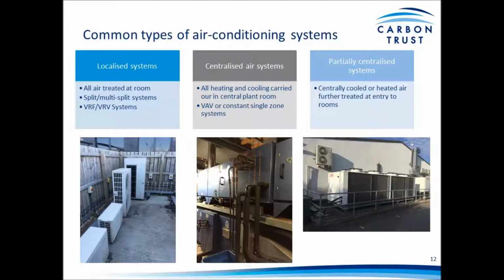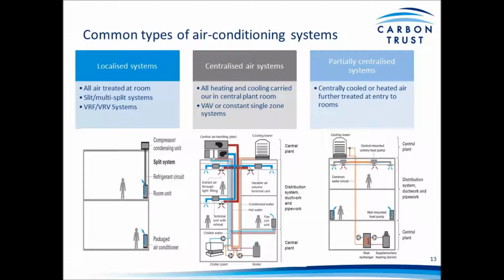Large office type accommodation may have all air treated, heated or cooled at the air handling unit in the plant room before it is distributed through the ductwork. These are more what we call centralized systems, and then you may get partially centralized systems, which can be a mix of the two, treating some air at the plant room to distribute and treating some air locally via fan coil units or local radiators, etc. And these diagrams just give a bit more of an illustration of the descriptions above if the images aren't familiar. Again, localized systems being the most common, with larger offices tending to have the centralized or partially centralized systems.